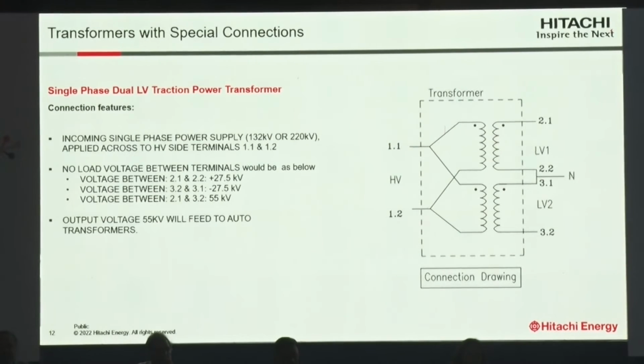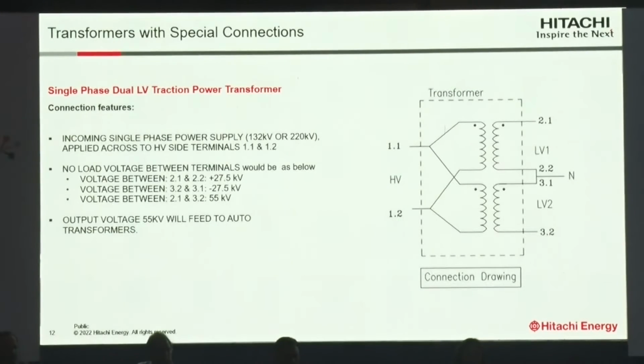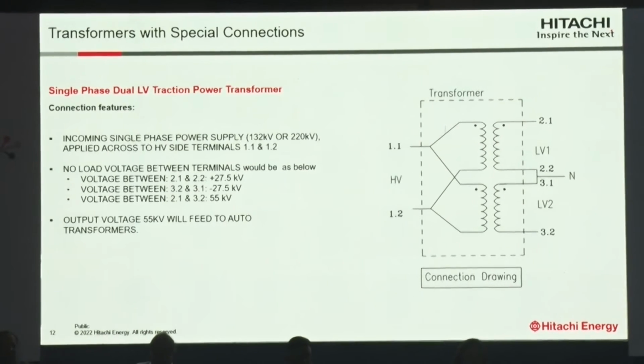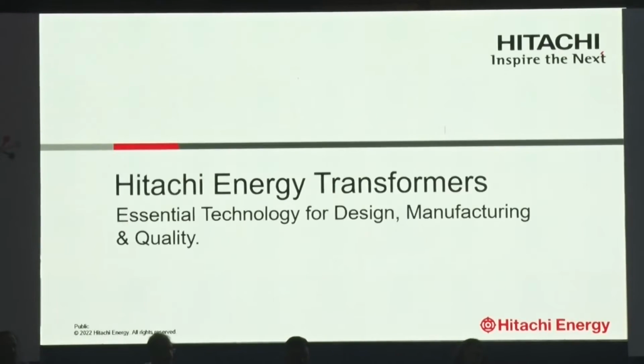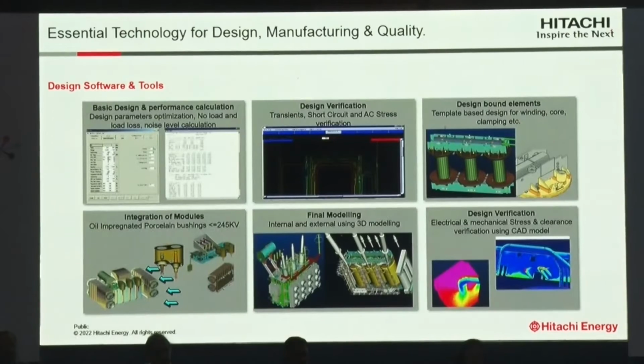Here we have two single-phase transformers connected such that between LV1 and LV2 we have 50 kV, but with a center point where one side is plus 25 kV and the other side is minus 25 kV. That's how the balancing happens, giving a very regulated voltage across the system.